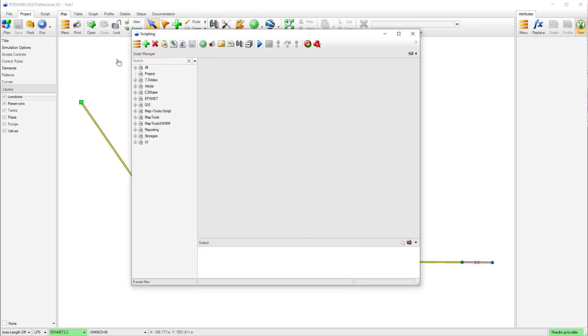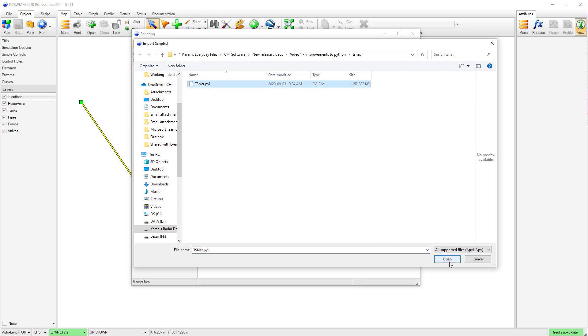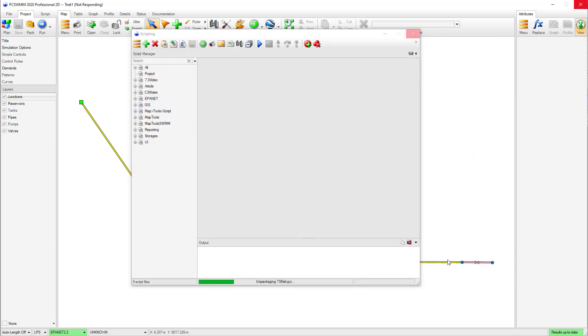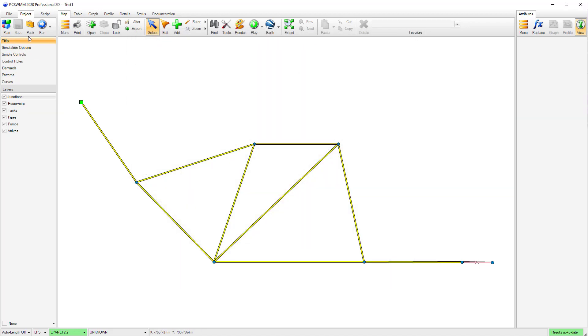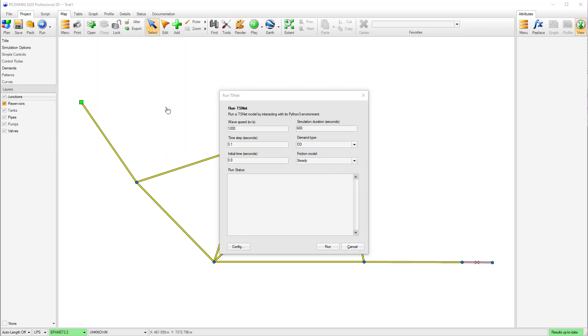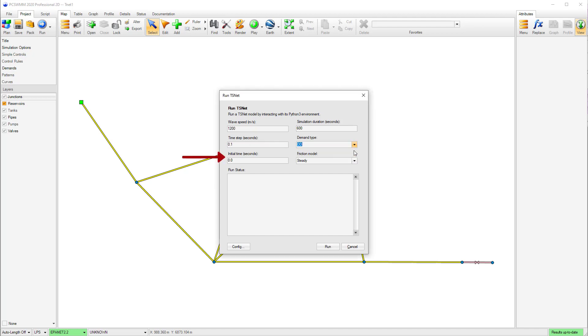I can also perform an analysis using third-party engines. For example, I can use a transient analysis tool created by the University of Texas at Austin to perform an analysis looking at the effects of turning off a valve in an existing EPANET model. When I do, I must first define an initial state — in this case the wave speed — as well as the simulation duration, time step, the demand type (either demand-driven or pressure-driven), initial time or when you want to start the simulation, and the friction model, with options including steady state, quasi-steady, or unsteady.